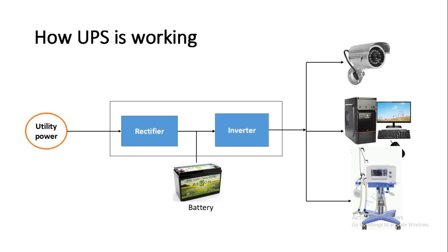Now we will see how UPS is working. See this picture — this is the main power supply connected to the UPS. Inside this UPS unit there is a rectifier unit and an inverter unit. The rectifier converts AC supply into DC supply. The main utility AC supply is connected to the rectifier, so it converts AC into DC. That DC supply is saved into the battery, and then it is also connected to the inverter. The inverter converts DC back into AC, and that AC supply is connected to the load — such as computers, medical equipment, CCTV cameras, and other equipment.